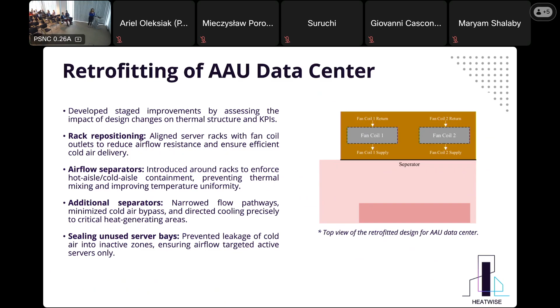The additional separators are added. So narrowed flow pathways minimize cold air bypass and directed cooling precisely to critical heat generating areas. And we did the same thing. Sealing unused server bays prevented leakage of cold air into inactive zones, ensuring airflow targeted active servers only. So it is really, I think, useful. This is the layout you can see.